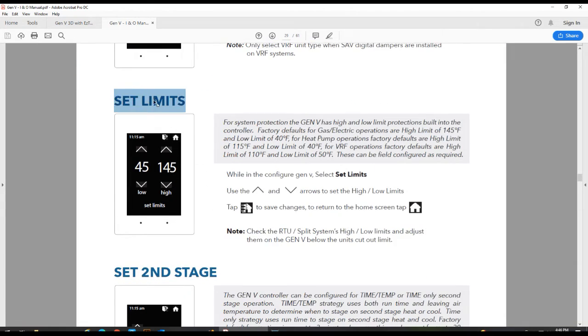Your limits. So setting our limits, if you set them for the factory default 45 and 145, this will simply protect your system from overheating or overcooling. So if we are cooling and we break the 45 degree low cutout, we will go ahead and go into a purge. We'll warm up your coil. After 5 minutes, we'll check that temperature again, and if it is warmed and above 45, we'll go ahead and bring the cool coil back in. And same thing for the high side if you break the 145. These are adjustable. So on the low side, it's adjustable from 40 to 50 degrees. And on the high side, it's adjustable from 100 to 160.